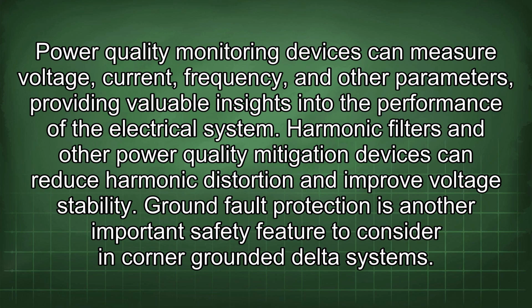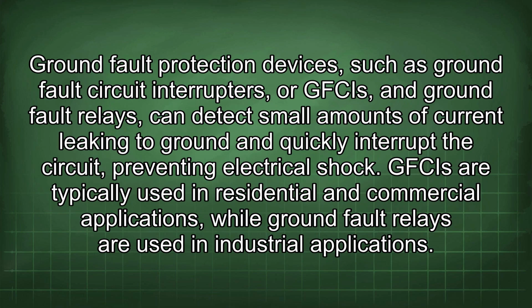Ground fault protection is another important safety feature to consider in corner-grounded delta systems. Ground fault protection devices such as ground fault circuit interrupters, or GFCIs, and ground fault relays can detect small amounts of current leaking to ground and quickly interrupt the circuit, preventing electrical shock. GFCIs are typically used in residential and commercial applications, while ground fault relays are used in industrial applications.